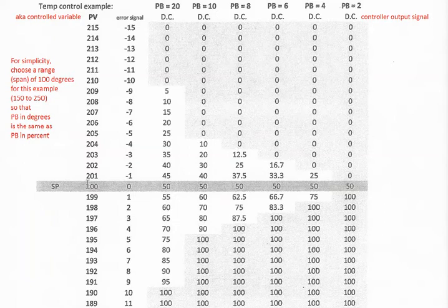And you can see as the process variable varies, if it's under the set point, as in down here, the appropriate error signal is generated. So if I'm 1 degree under set point, an error signal of 1, 2 degrees under set point, error signal of 2, and so forth. If I'm over the set point, a negative error signal is generated. So if I'm 1 degree over, I get a -1 for my error signal, and so on. So those are all written out for us.